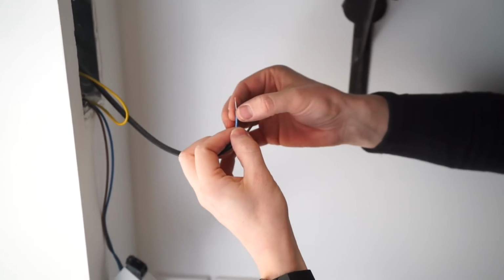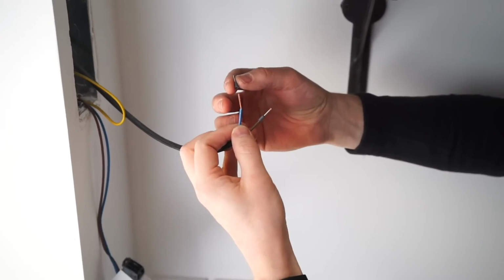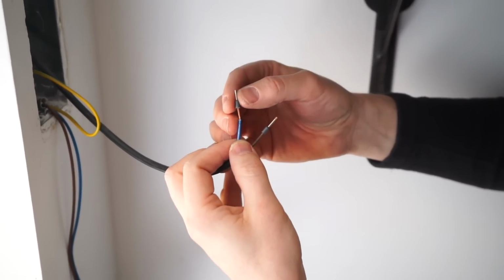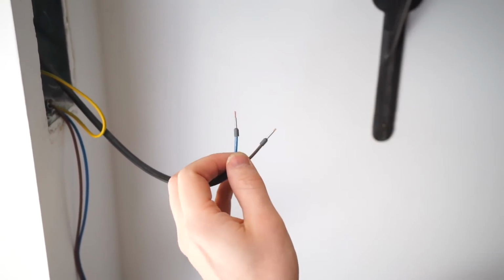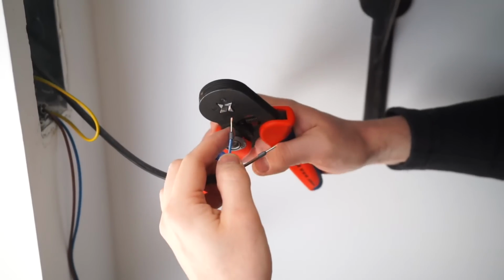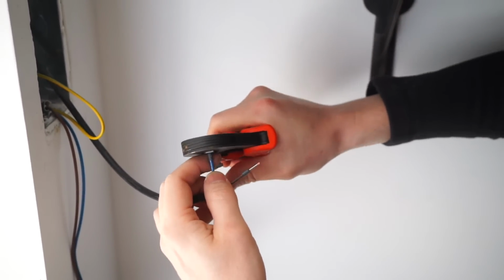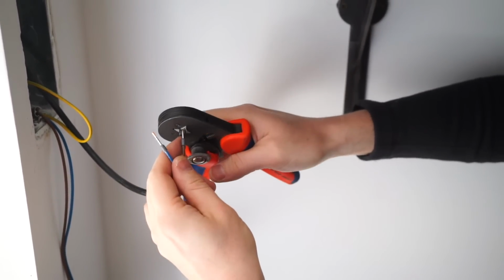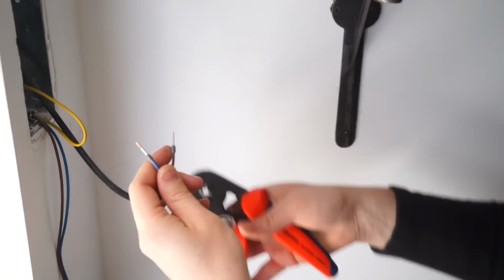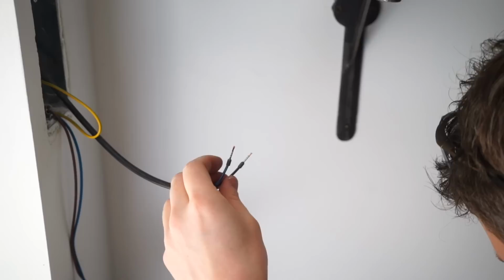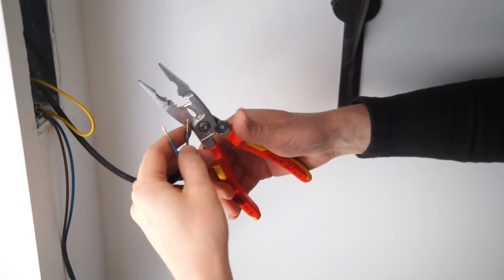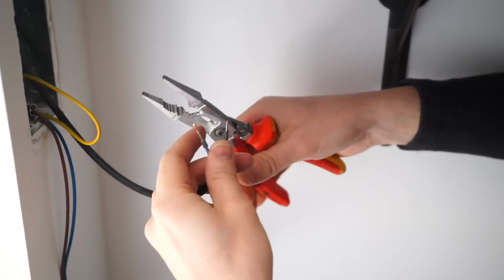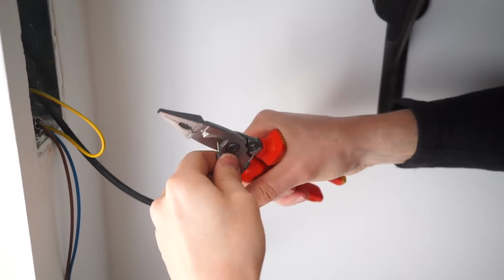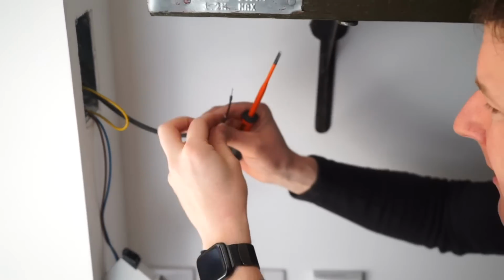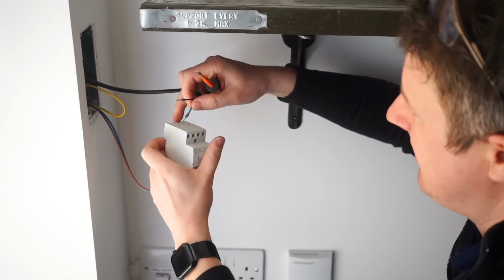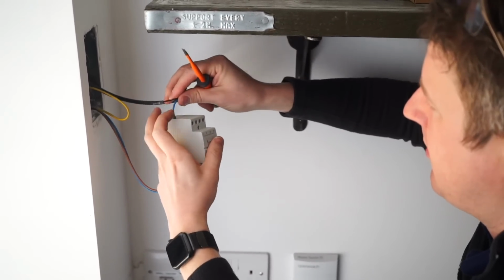Because it's fine stranded cable, we use these ferrules, slide them over, and crimp them on using this ferrule crimping tool, then cut off the excess. That means when you tighten up the terminals, you don't get the cable fraying all over the place.